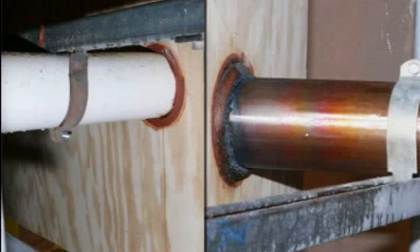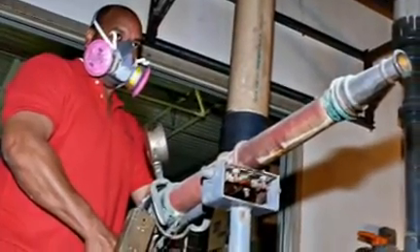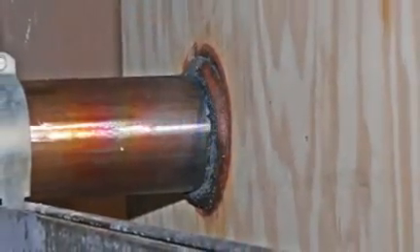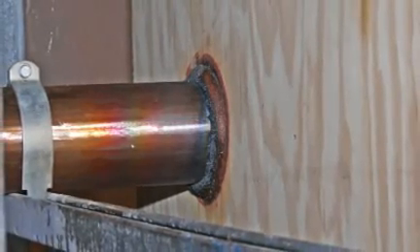This seal must be maintained for a specific period of time at a specified temperature in order to earn a 1, 2 or 3 hour rating. To pass the test and be approved as a UL listed system, an opening cannot be produced through which there could be a projection of water. If inspection shows that no openings have been created by the hose stream, the fire stop system passes. As you can see, the Rector Seal fire stop products used in this system passed and did not allow the passage of water through any openings.